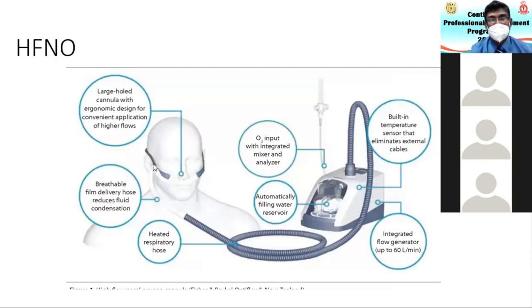This is the cannula, high flow cannula. This is the heated hose, and then this machine delivers. This is the humidifier, it can add some water vapor into the circulating breathing circuit. And this is the flow meter, which can deliver high flow, up to 60 liters per minute.